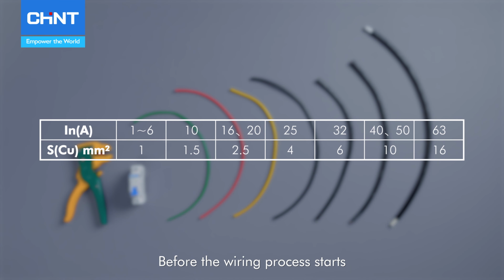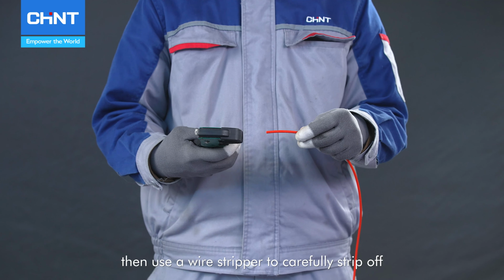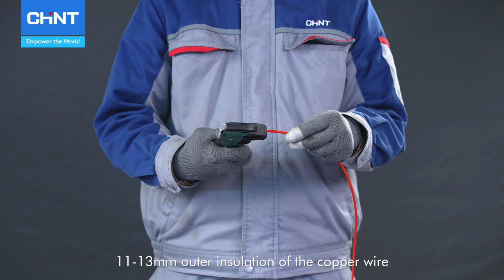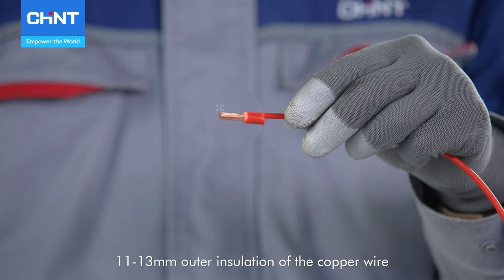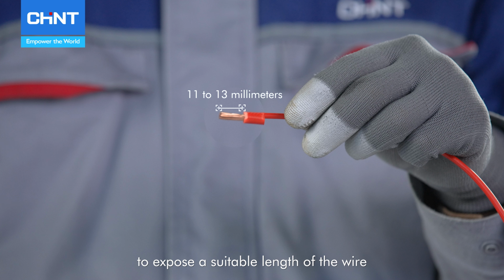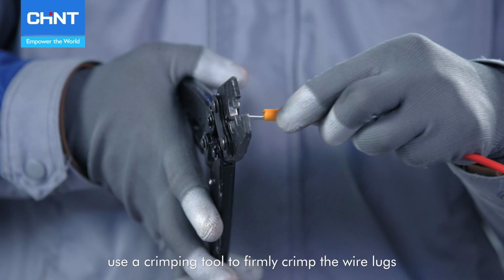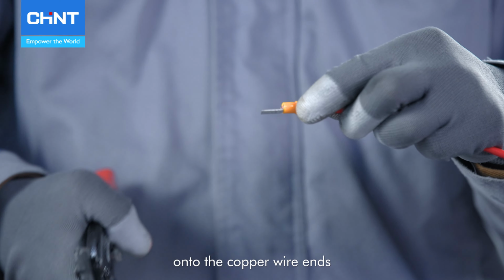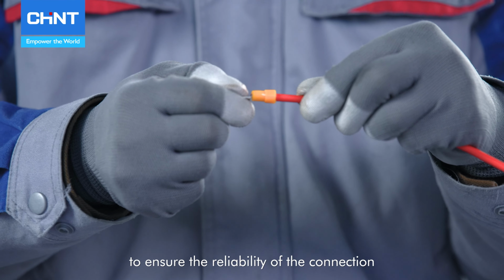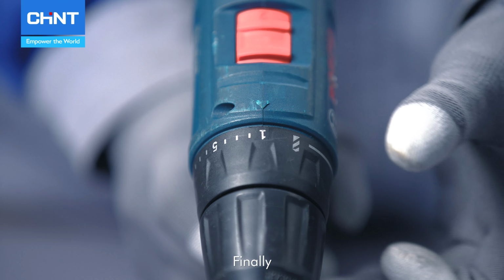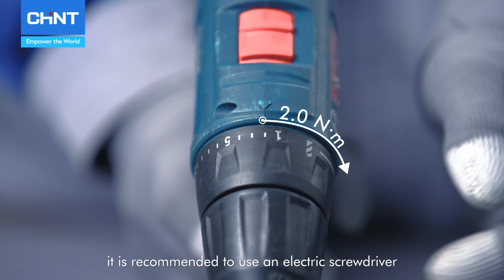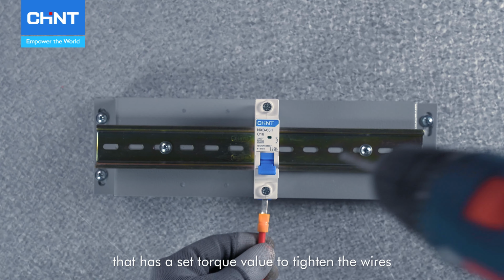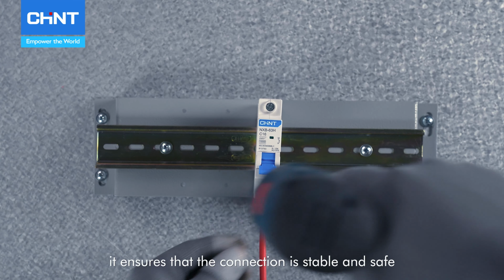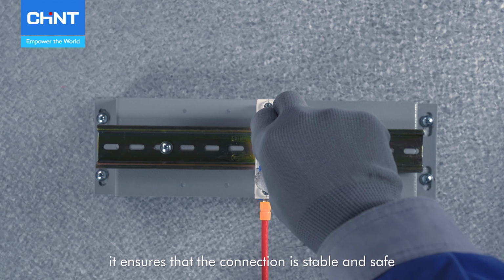Before the wiring process starts, choose wires with the appropriate cross-sectional area based on the product's current rating, then use a wire stripper to carefully strip off 11 to 13 mm of outer insulation of the copper wire to expose a suitable length of the wire. Next, use a crimping tool to firmly crimp the wire lugs onto the copper wire ends to ensure the reliability of the connection. Finally, it is recommended to use an electric screwdriver that has a set torque value to tighten the wires. This is important because it ensures that the connection is stable and safe.